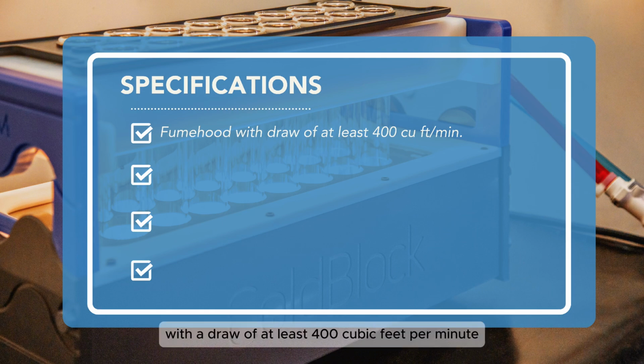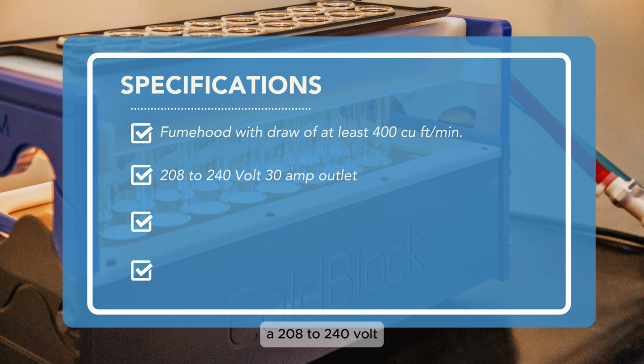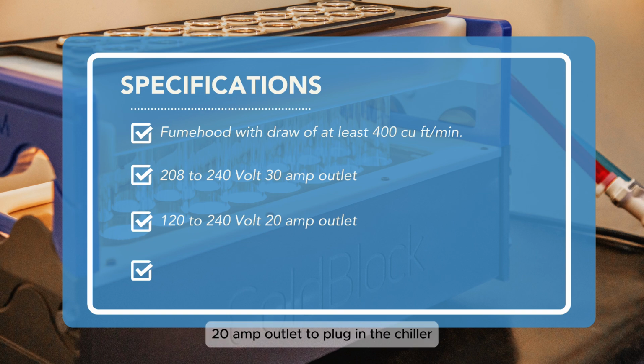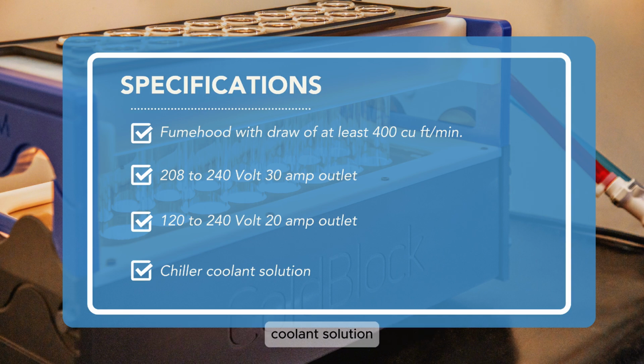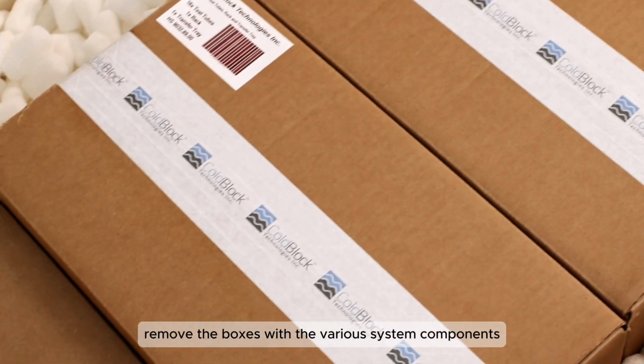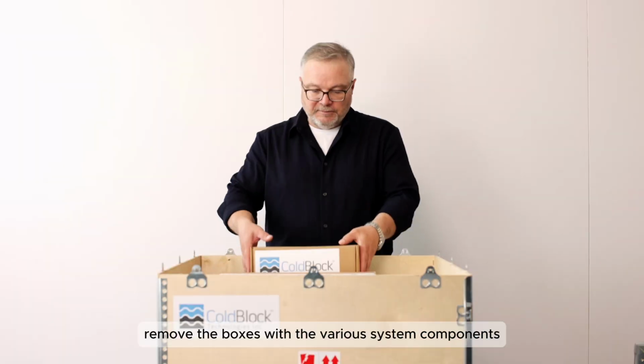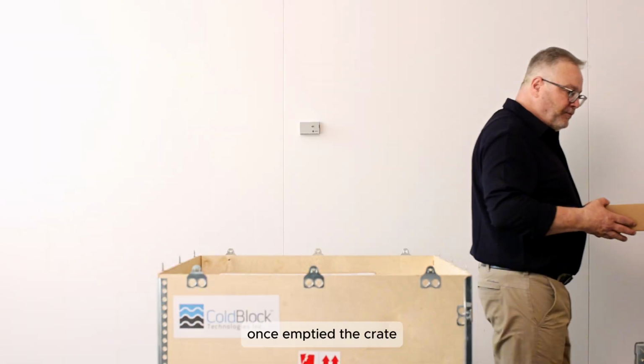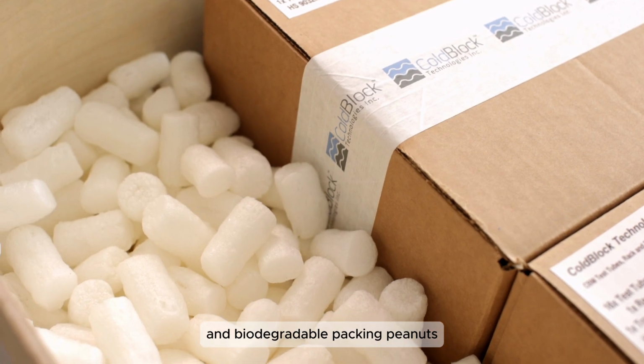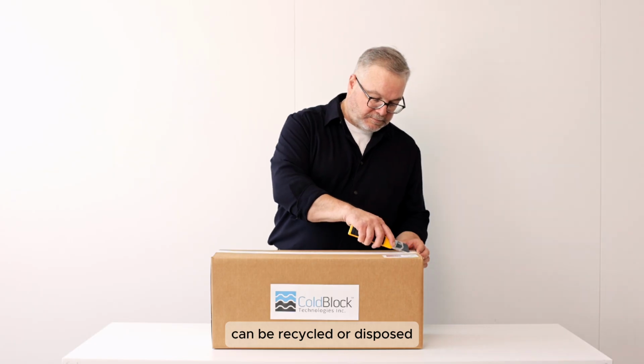A fume hood with a draw of at least 400 cubic feet per minute, a 208 to 240 volt 30 amp outlet to plug in the controller, a 120 volt or 240 volt 20 amp outlet to plug in the chiller. Ensure that you have a suitable chiller coolant solution. Carefully remove the boxes with the various system components. Once emptied, the crate and biodegradable packing peanuts can be recycled or disposed.